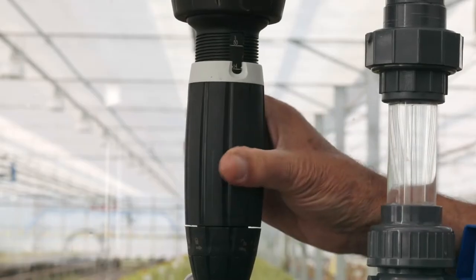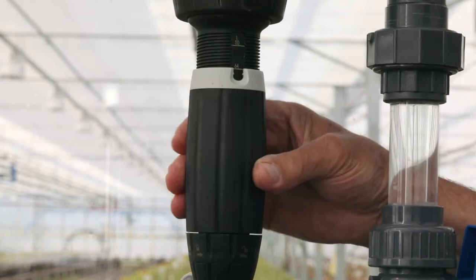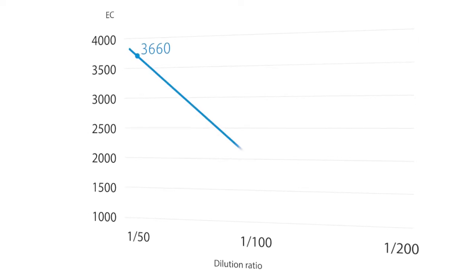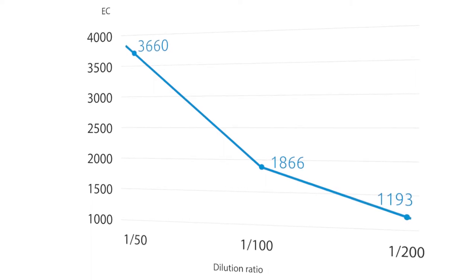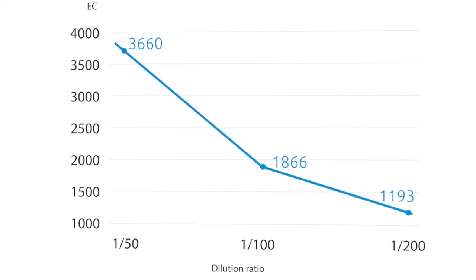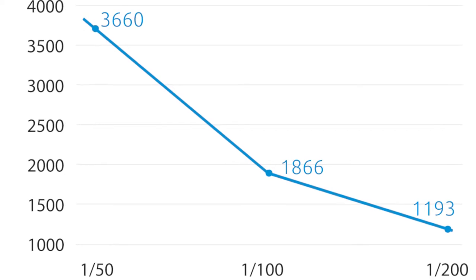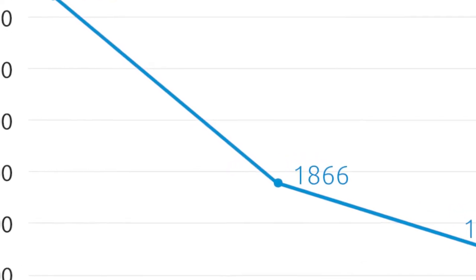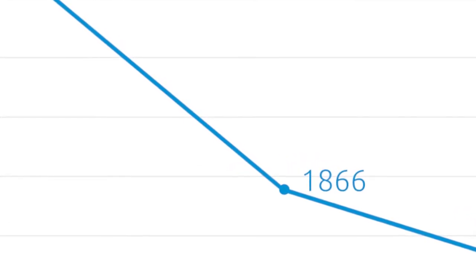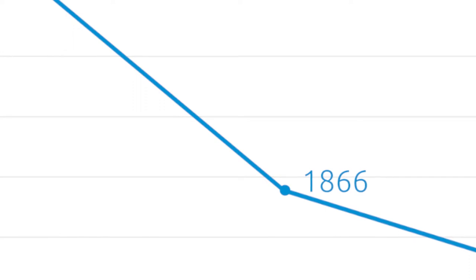We're going to run the diluter at one in one hundred one percent dilution and see if it actually gives us an output solution with a reading of approximately one thousand eight hundred microsiemens. This will tell us whether or not the diluter is actually working normally.